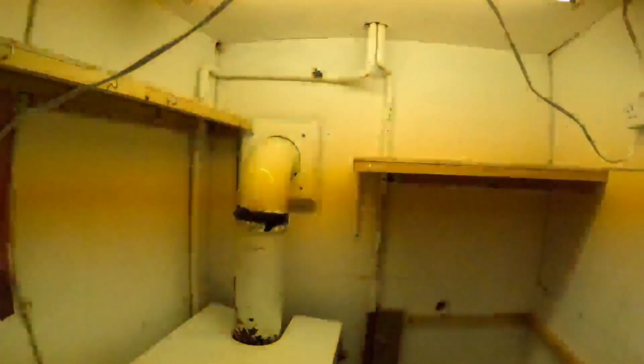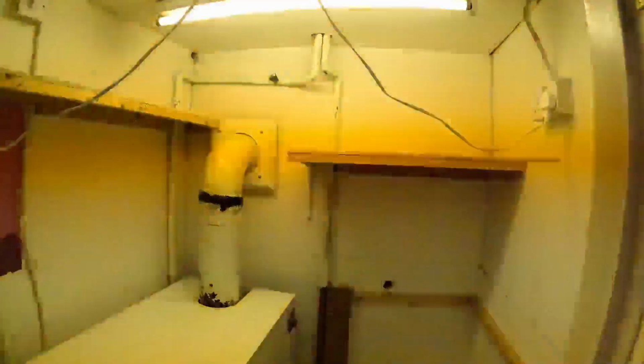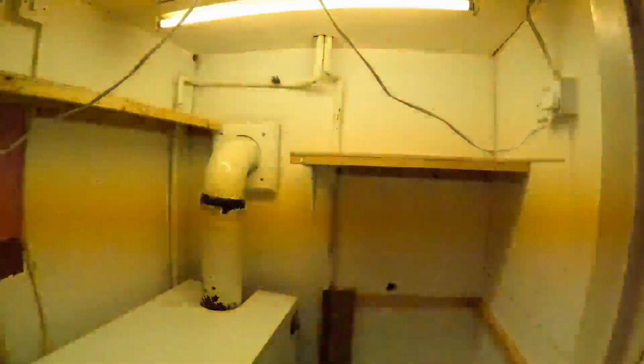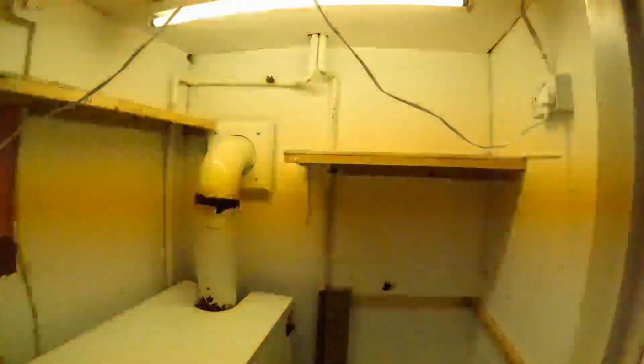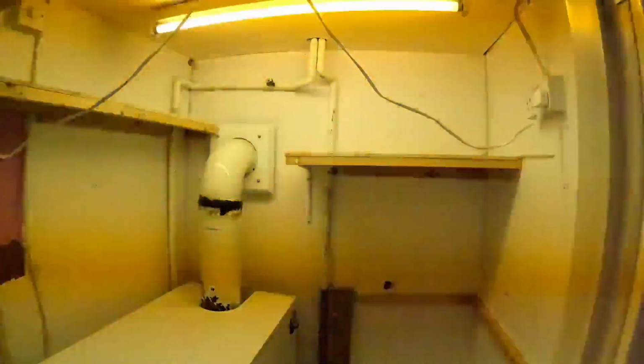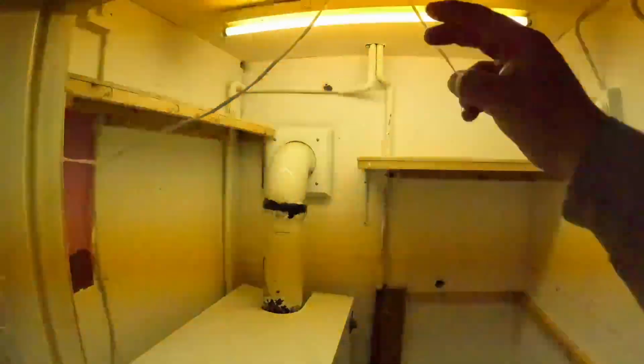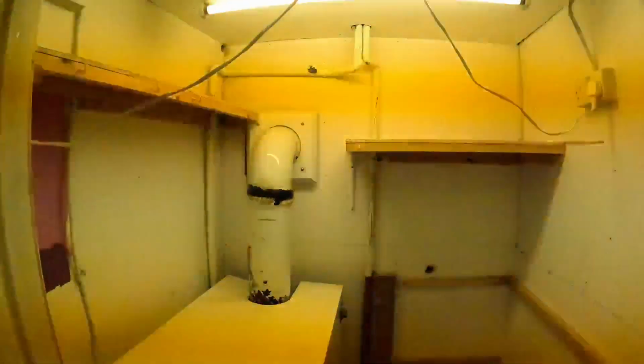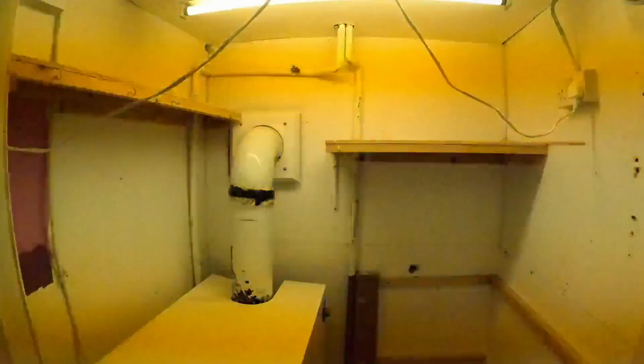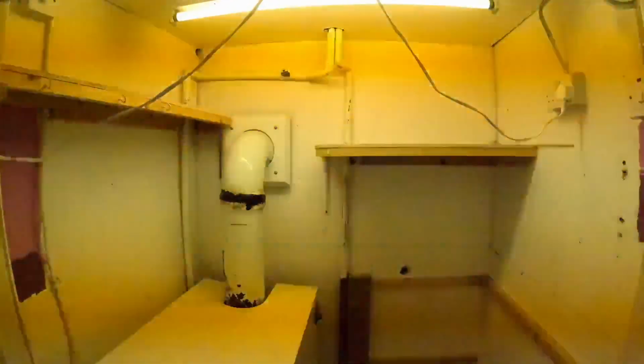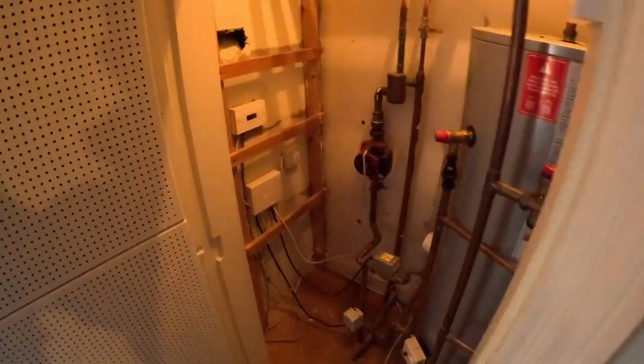Right above here is the airing cupboard, which I'll run up to in a minute. Hopefully we'll fit the air separator, the filter, pump, and the separate pump for the other side of the plate heat exchanger. Then all they're going to have down here is 2 pipes in that corner. It's about 1.2 metres wide, so they should get a nice fridge freezer in here, and it'll be a usable cupboard again. So this is the airing cupboard.